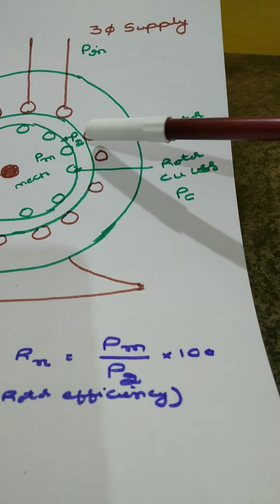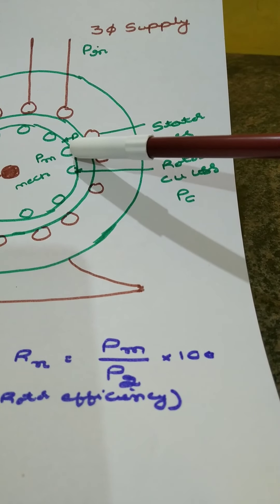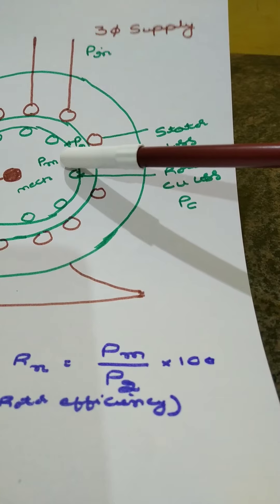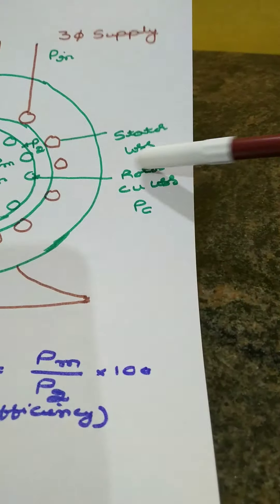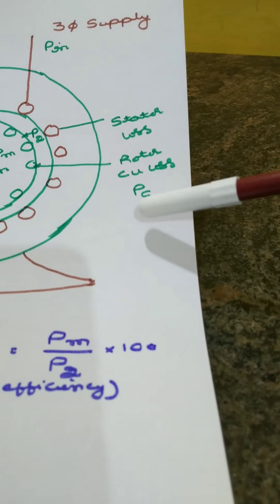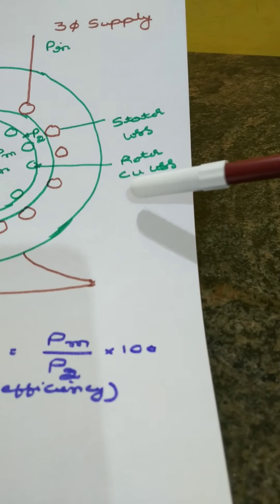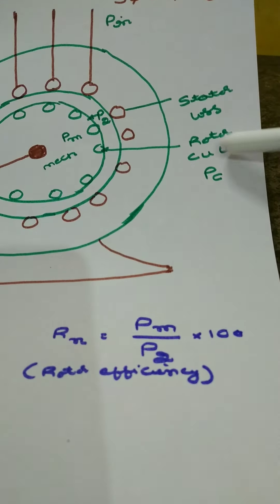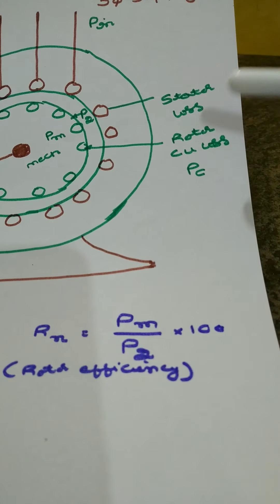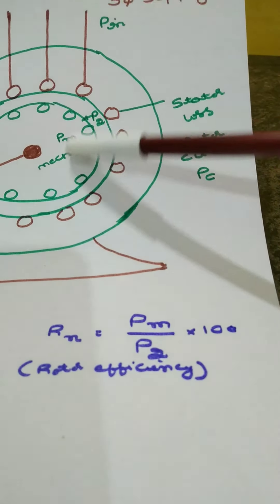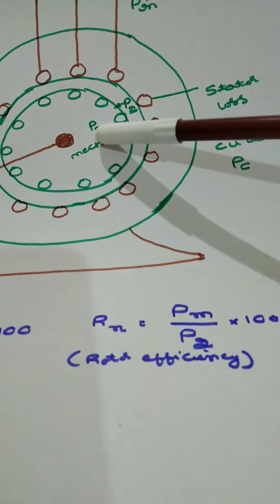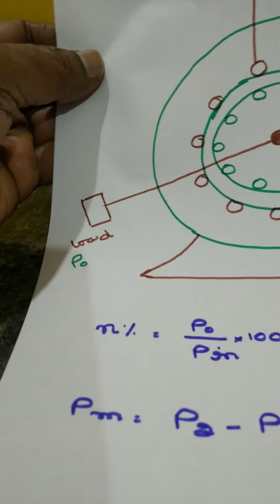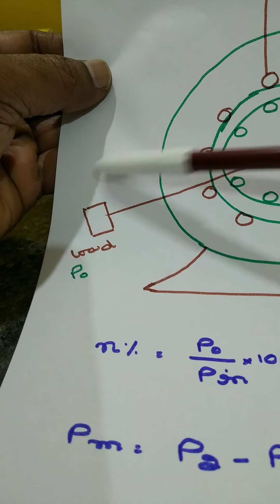The output from the stator — or rotor input — is P2. In the rotor winding, current flows and rotor copper losses occur, represented by PC. Rotor core loss is neglected because under running condition frequency is less. P2 minus PC gives the gross mechanical power developed, called PM. PM minus friction and windage losses gives the shaft power at the load — this is the useful power at the load side.